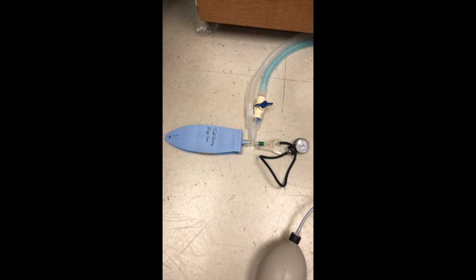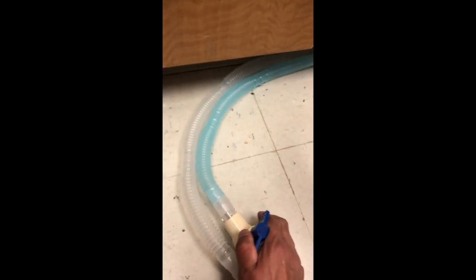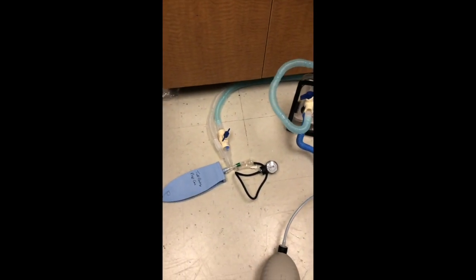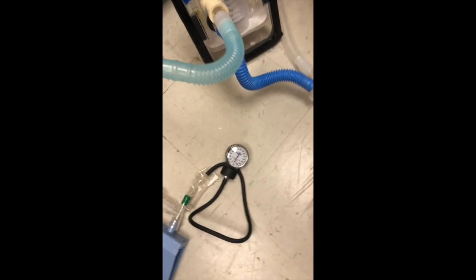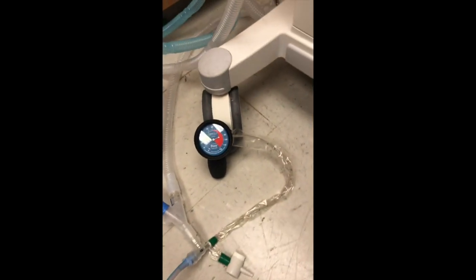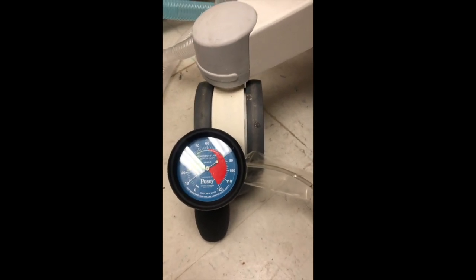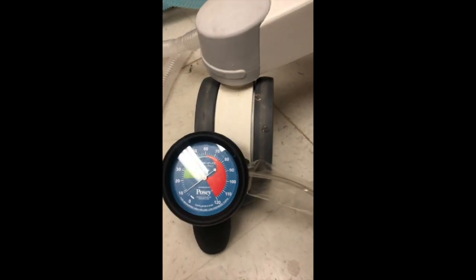The only difference with the sphygmomanometer is that it is measured in mercury, so therefore we have to convert it into water. But if we don't have the gauge to measure cuff pressure, we can use this gauge. And again, I would change the valve to demonstrate how easily we can individualize pressure or volume to a patient. So I have opened the valve a little. If you see, the volume has already increased in the second lung, and if you see, the peak pressure also would increase here. It's almost going to 32. And if you see on the other artificial lung, the peak and the PEEP stay the same.